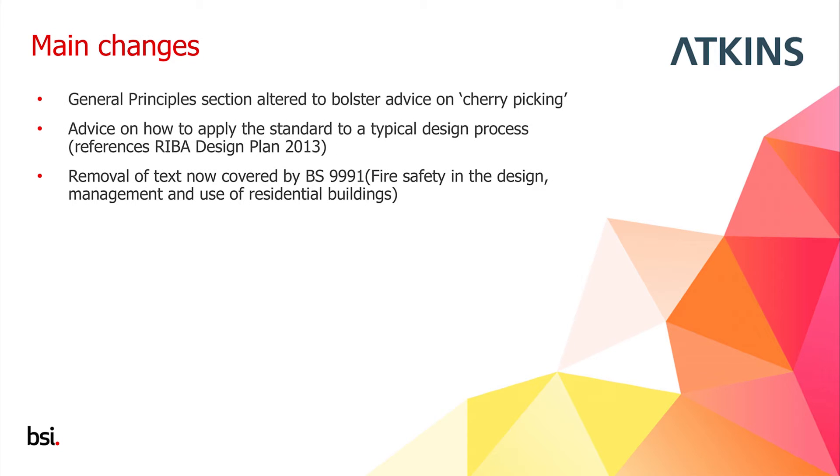Text covered by BS9991 — fire safety in the design, management, and use of residential buildings — has been removed from BS9999. Residential buildings used to be covered in BS9999 and BS5588 Part 1, but standalone residential design is now in the separate standard BS9991. However, guidance on residential aspects has been retained where it applies to mixed-use buildings — for example, retail on the ground floor, offices above, and residential at the top — which is very common in towns and cities.